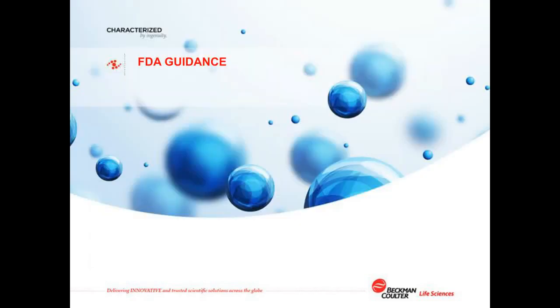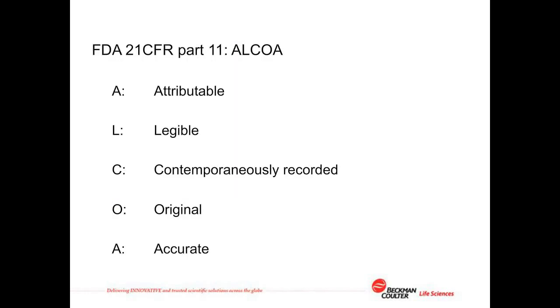So let's take a look at what other guidance the FDA gives on this topic. In their 2003 guidance on the implementation of their 21 CFR Part 11 data integrity rule, the FDA used the acronym ALCOA, where they define good data integrity practice as creating records that are attributable to the technician carrying out the testing, are legible, are created contemporaneously, are original, and accurate.